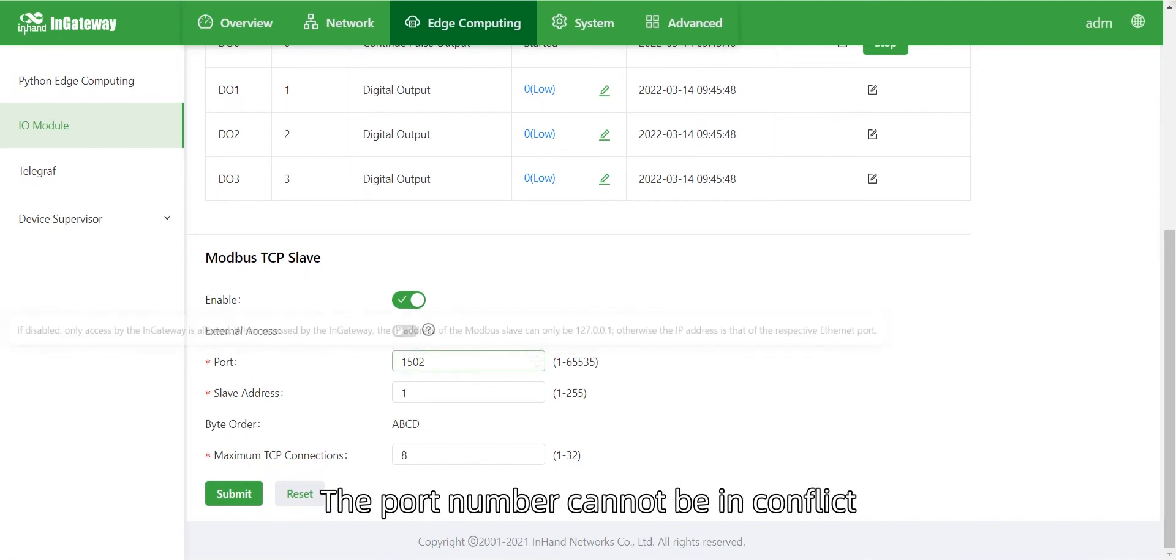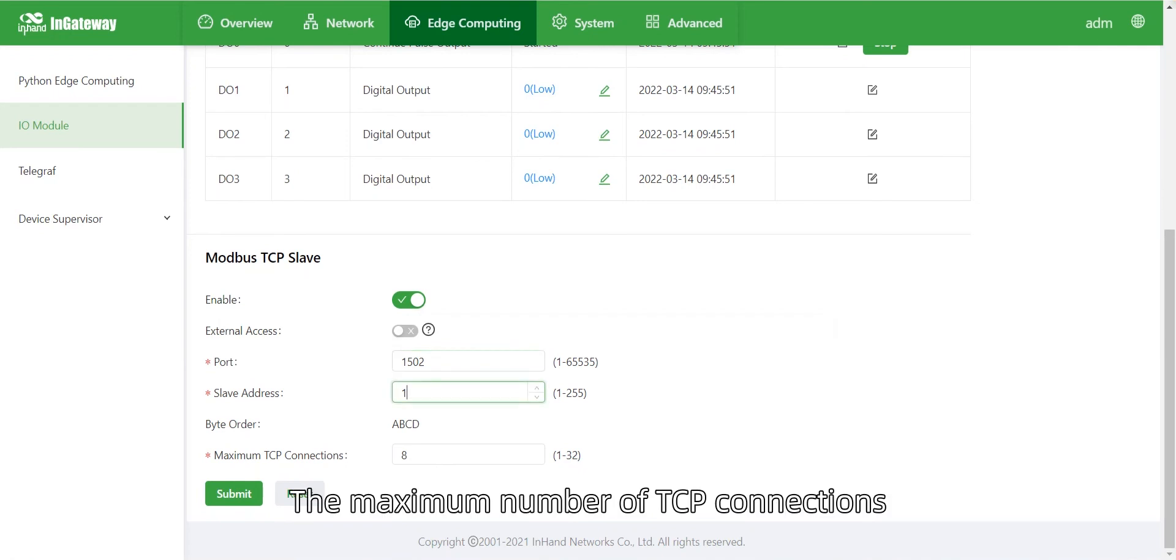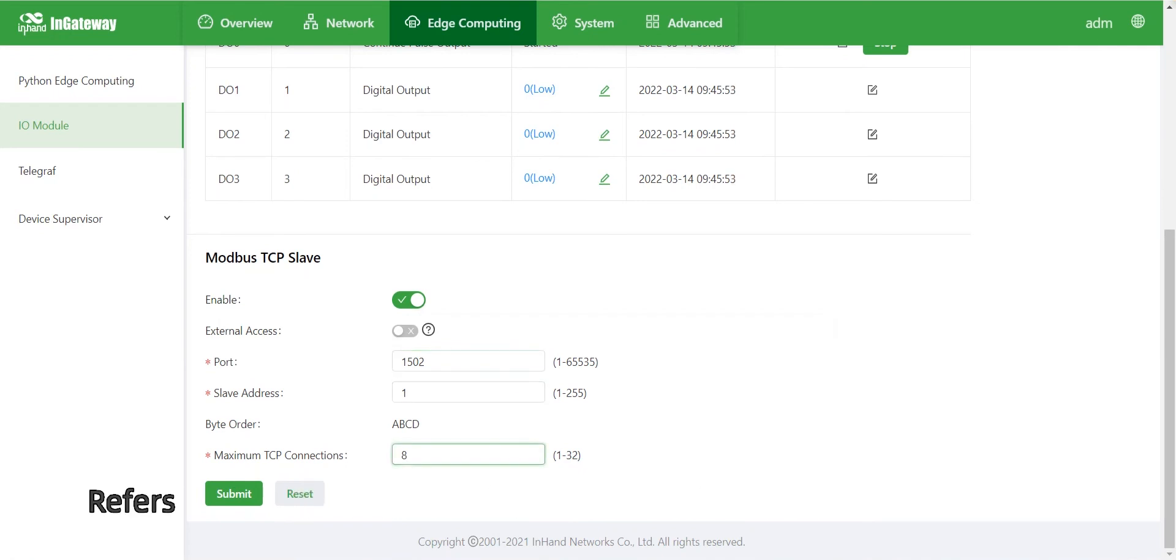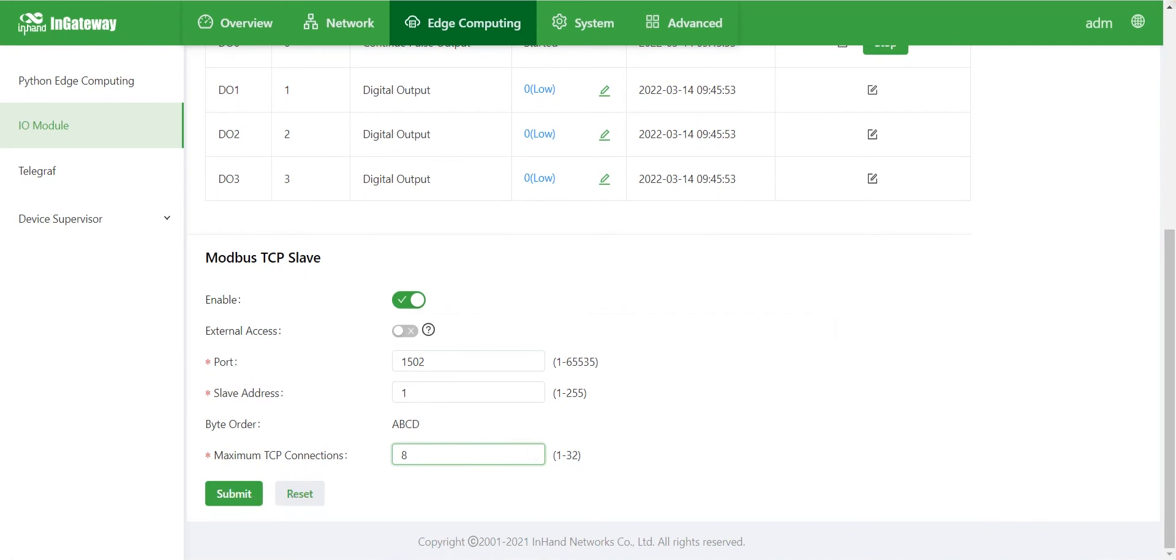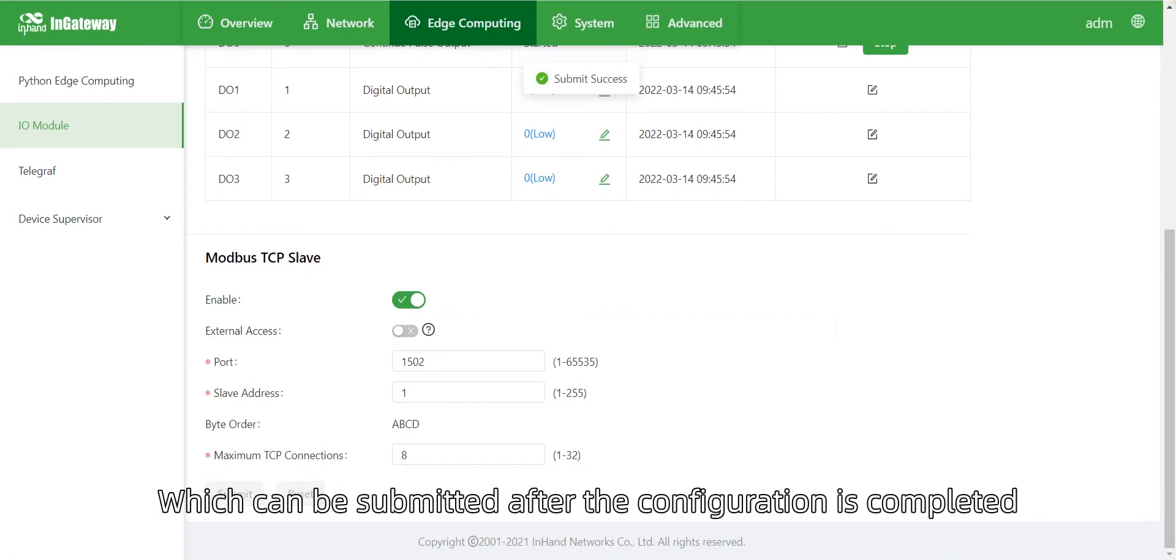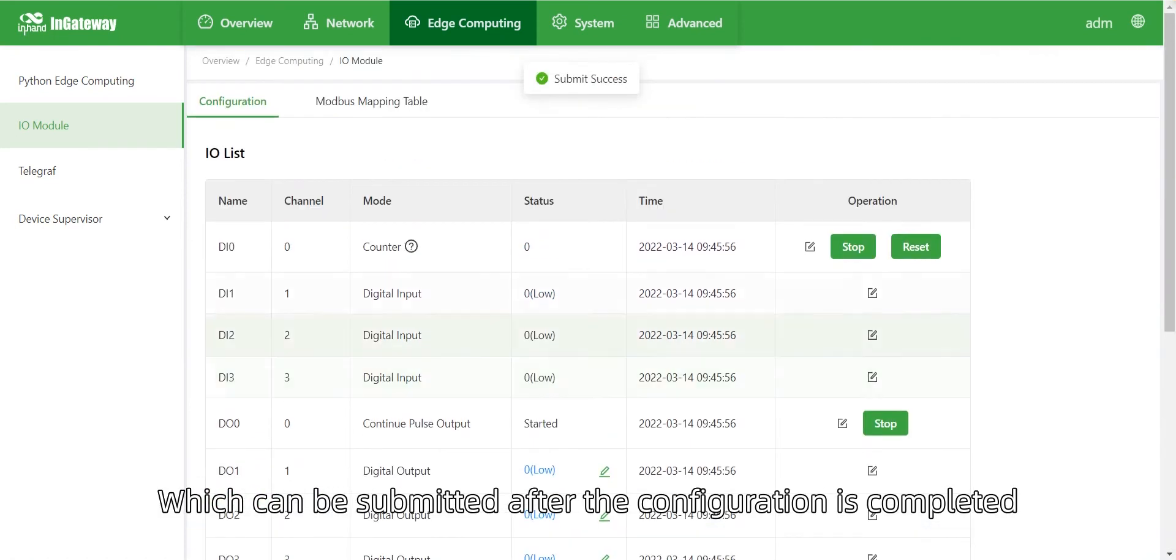Port number, slave address, and byte order are the connection information of Modbus TCP. Please note that the port number cannot conflict with other programs or functions. The maximum number of TCP connections refers to the maximum number of Modbus TCP connections supported, which can be submitted after configuration is completed.